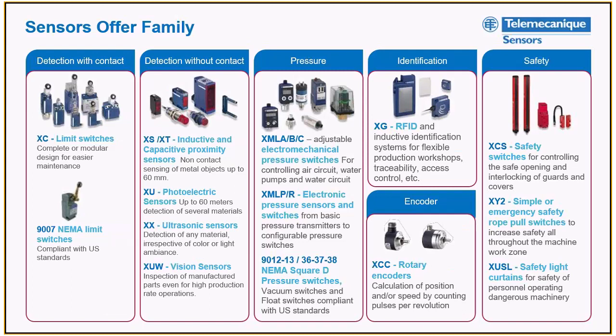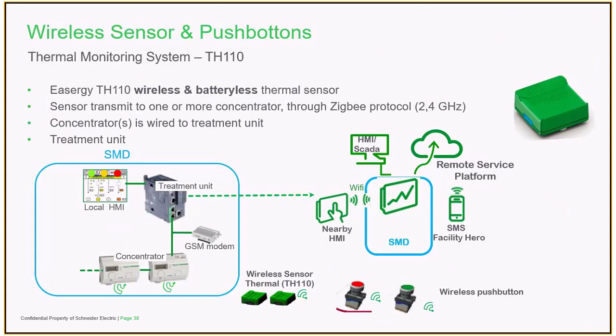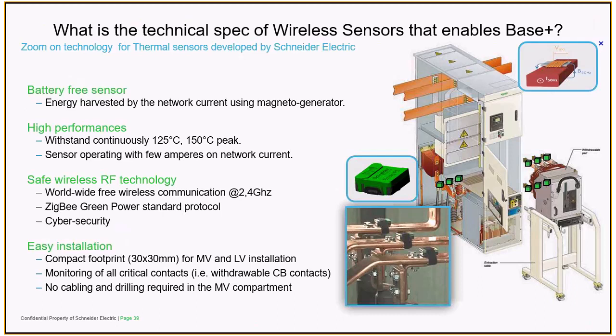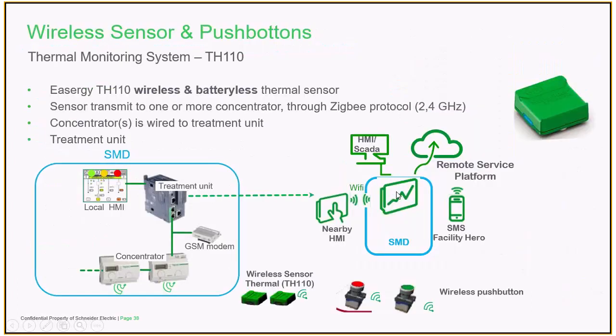Next, what about temperature and humidity monitoring? These are some sensors we use especially in data center applications. What's the use case? For example, if I want to measure the bus bar temperature of my electrical panel, I can engage these sensors directly on the bus bar and measure the temperature in each phase, and this signal transfers to a concentrator like this.